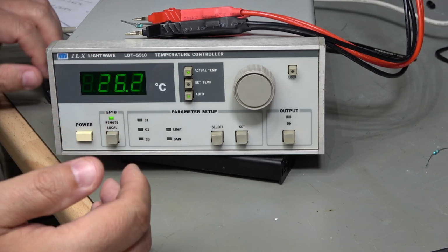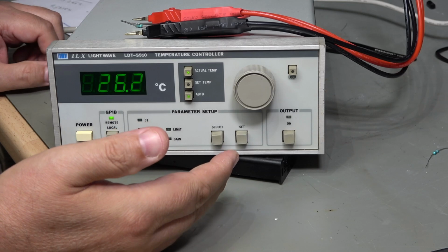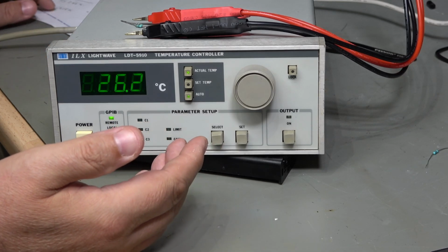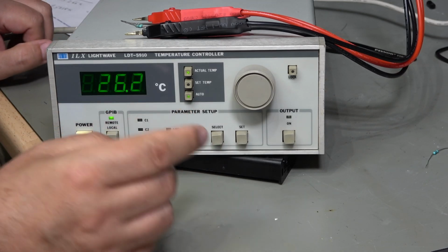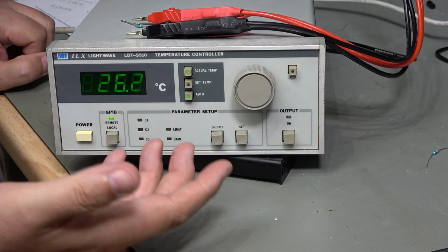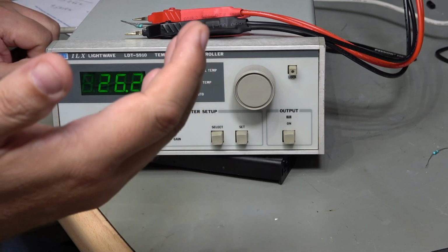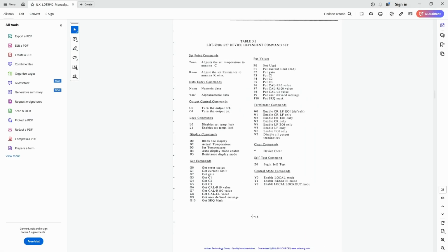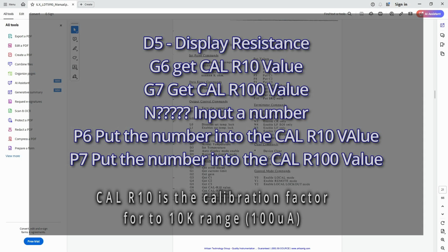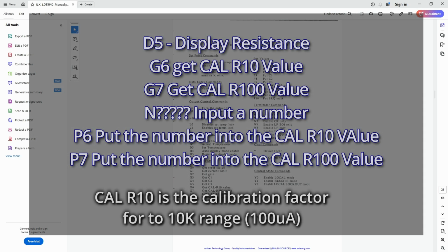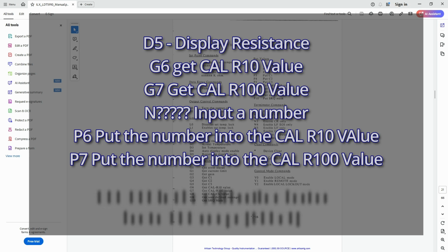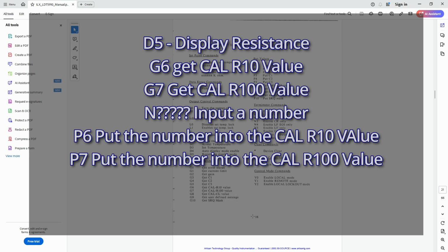So currently we're on the 100 microamp range, and we've got a 9.5218k resistor attached. So we want it to read 9.522. I have got a manual with all the commands in. So we're doing the Cal R10 value. So I need G6 and P6. So G6 is going to get the calibration value for the resistor 10 range. Before we do that, we need to find out what we think the resistance is.